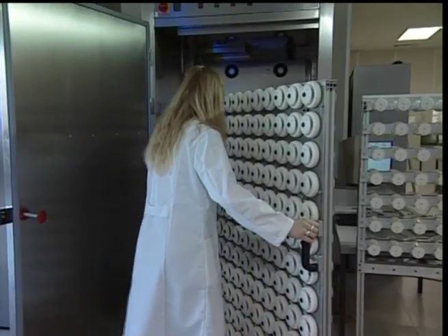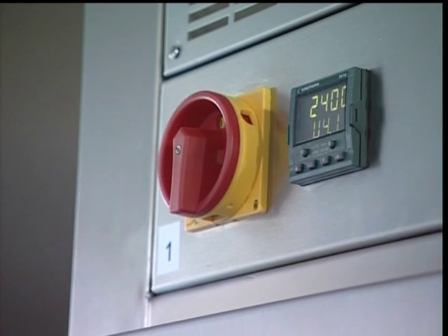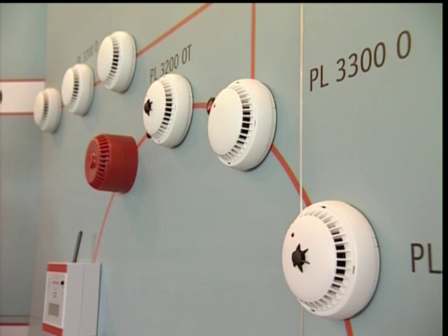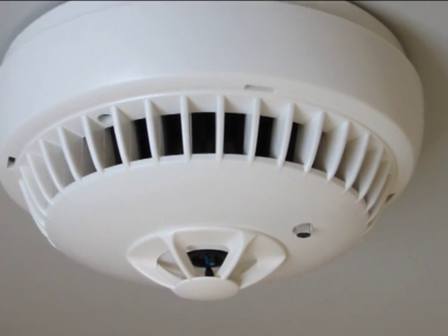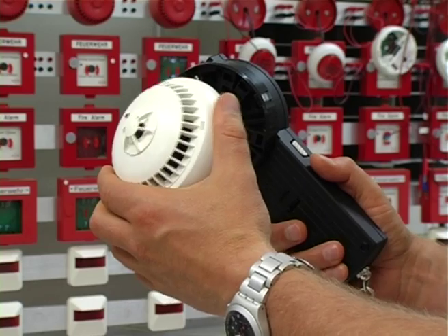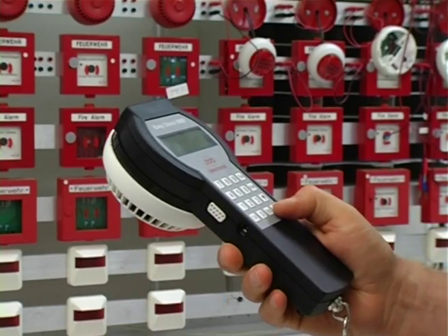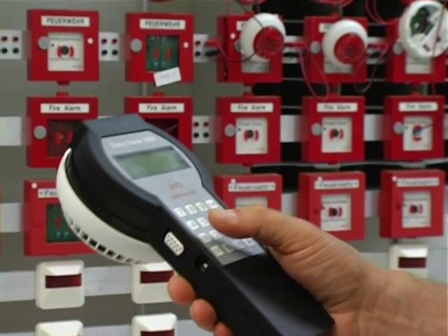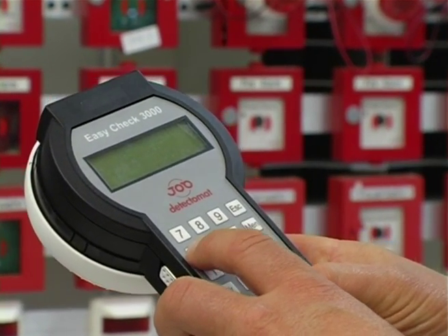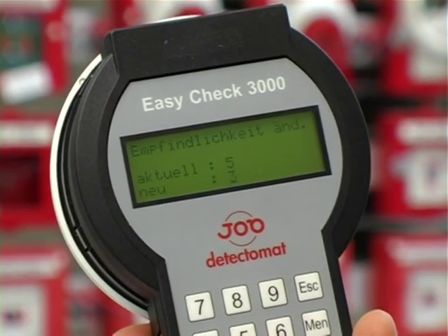Two temperature sensors with fast and highly sensitive measuring accuracy analyze the ambient temperatures. Via intelligent algorithms, the detector can be operated according to the maximum, rate of rise, or combined analysis. Setting is done by programming different sensitivities. By this exact adjustment possibility to environmental conditions, the detector precisely detects in case of a fire and excludes false alarms by means of several types of temperature measurements.